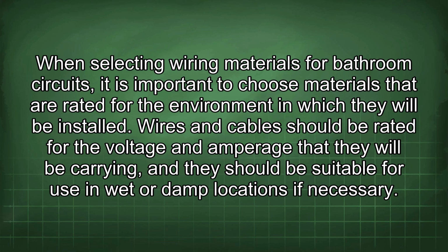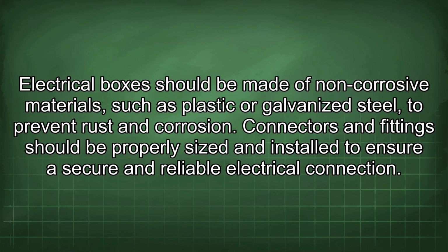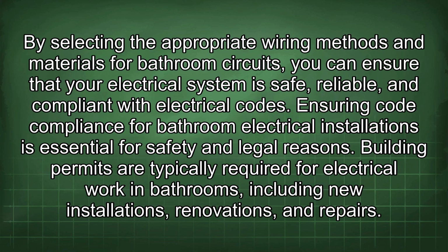Wires and cable should be rated for the voltage and amperage that they will be carrying, and they should be suitable for use in wet or damp locations if necessary. Electrical boxes should be made of non-corrosive materials, such as plastic or galvanized steel, to prevent rust and corrosion. Connectors and fittings should be properly sized and installed to ensure a secure and reliable electrical connection. By selecting the appropriate wiring methods and materials for bathroom circuits, you can ensure that your electrical system is safe, reliable, and compliant with electrical codes.